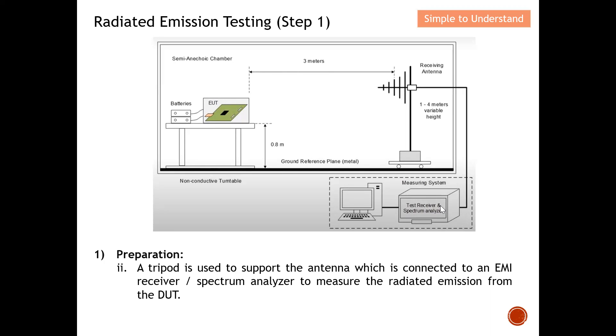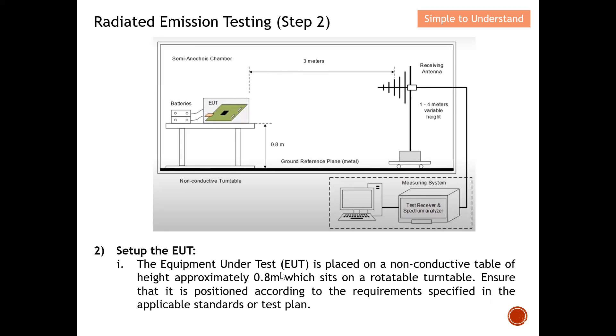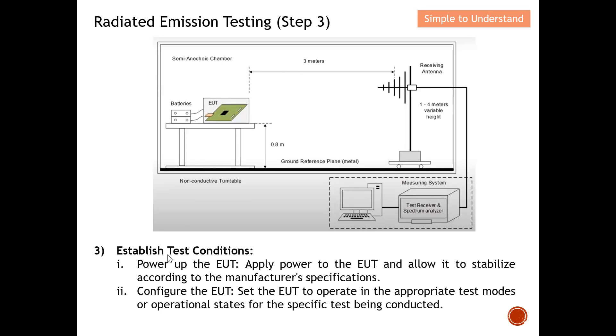Step 2: the EUT is placed on a non-conductive table — this cannot be metallic. Typically a special type of fiber is used as the table surface. The table height is approximately 0.8 meters, and it sits on a rotatable turntable that can turn 360 degrees. Ensure that your EUT is configured according to the requirements specified in the standard or the test plan.